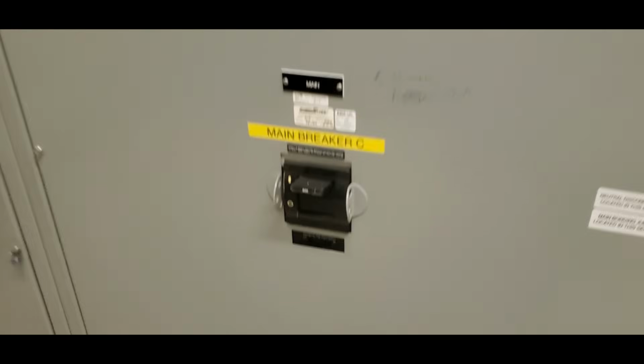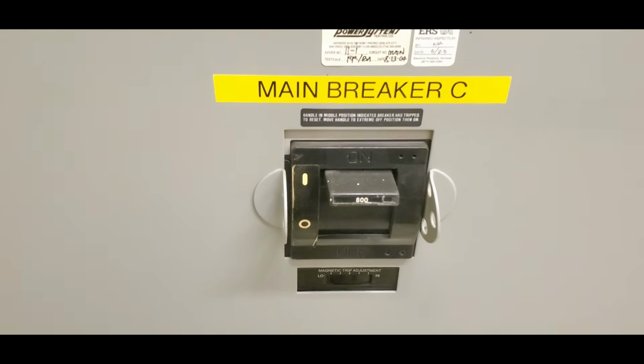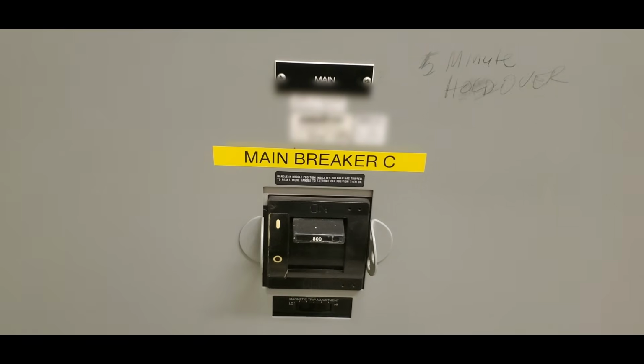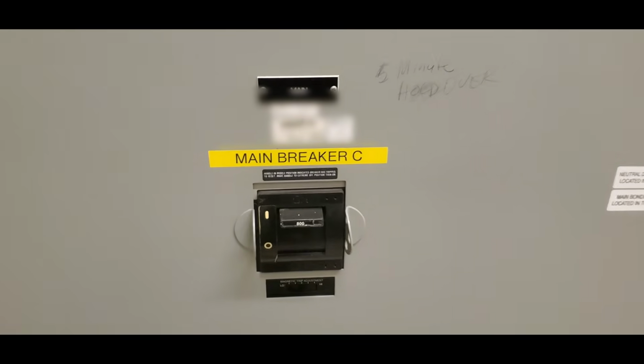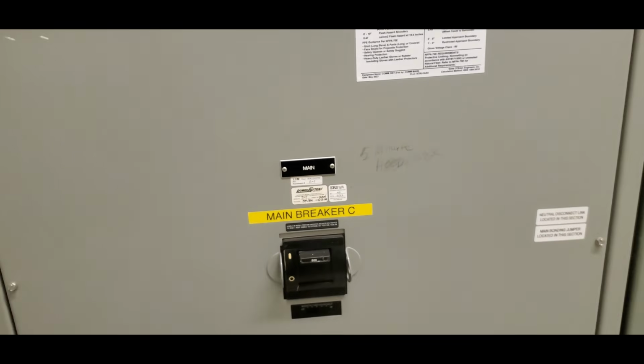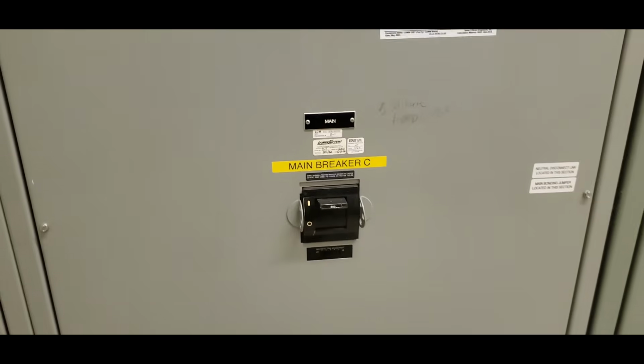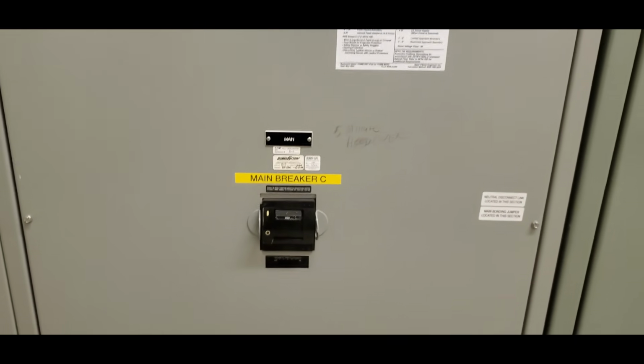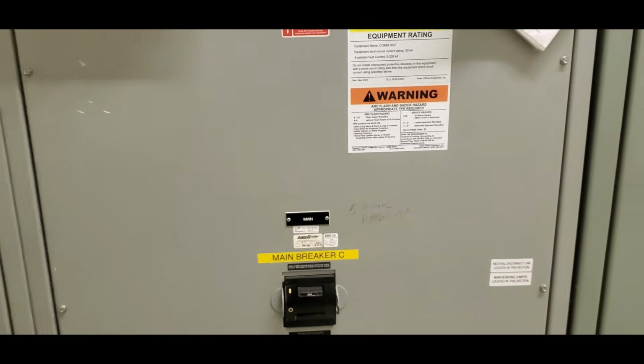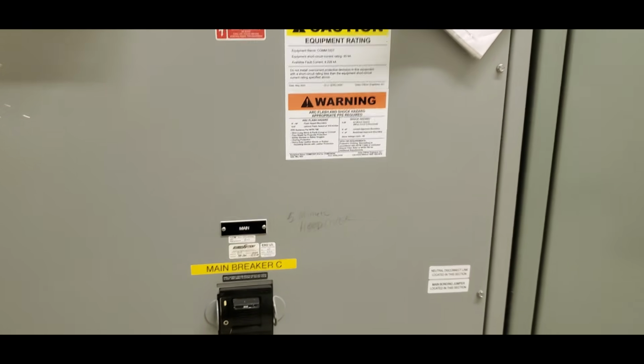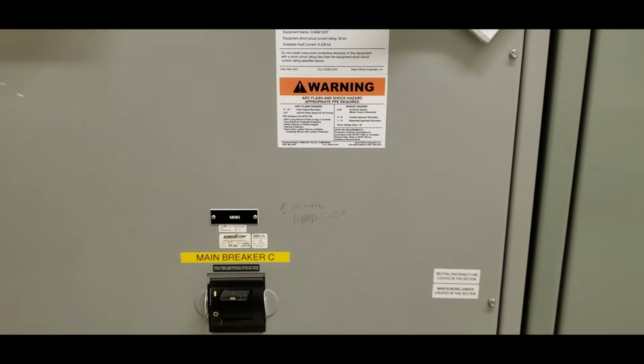And we come to this guy. Here is our breaker. It's an 800 amp breaker. And you can see why you would want to operate that thing manually to simulate a power failure. There is a pretty large arc flash on this thing, and you would have to wear the correct calorie suit and protection and gloves and all that stuff to switch these types of breakers. In our larger COs, we actually have air breakers where you pump the air, like in Jurassic Park. If you've ever seen that, those do exist. They're made by Siemens and probably other companies, where you pump the power for the spring, hit the switch, and it closes it.